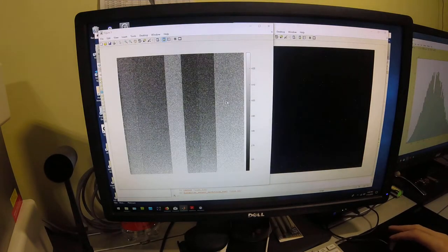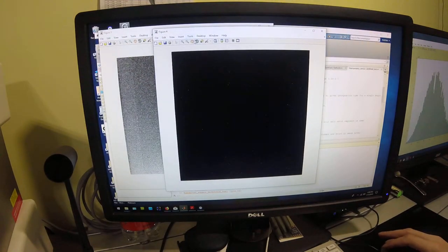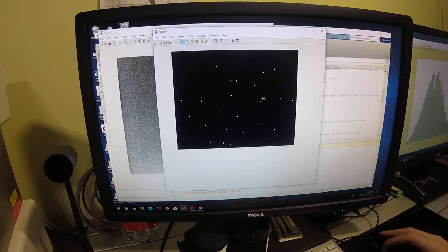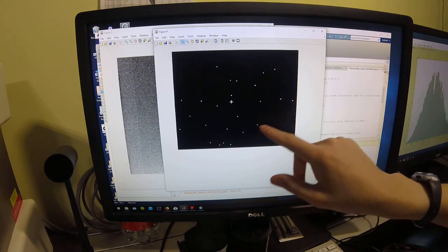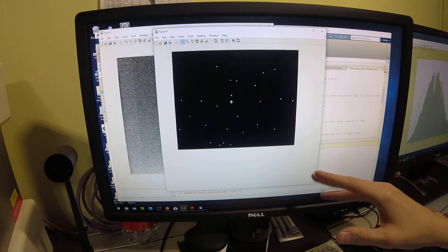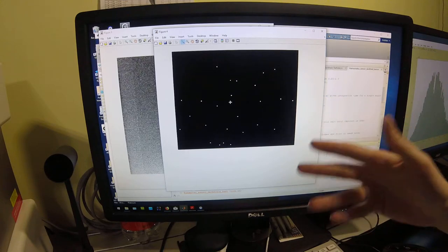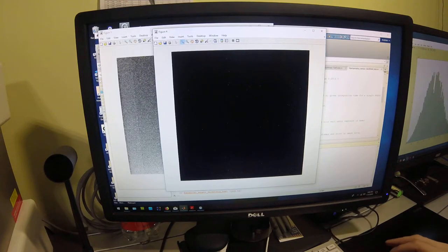Looking at plus or minus 2 standard deviations, we can see the dark field noise on the sensor. This is basically just dark current variations in the detector. Looking closer in on the defect map, this is anything outside plus or minus 5 standard deviations. We can see that it captures some of those dark field pixels which are very far out of the normalized histogram, so these are likely defective pixels. There are only around 150 of them on the sensor, which is fantastic. All sensors are going to have some defective pixels, and those can be corrected for later in processing.